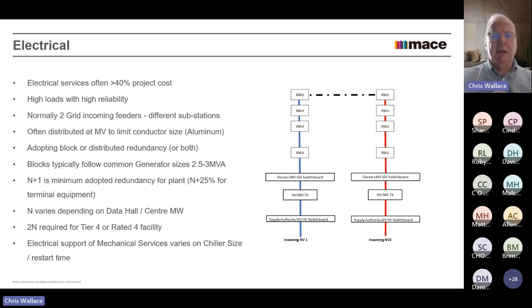And then what I've found over the years, and what's become more and more common, is you will run things through a series of ring main units. So you run rings, loops of ring main units. What you'll do is have the ring main unit loop fed from the two different feeds, but with an open section in it. Where the open section is depends on the design concept.